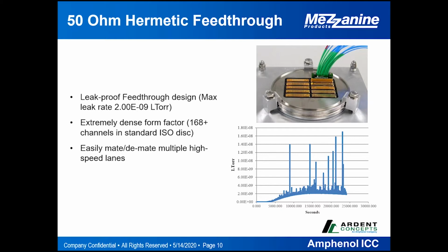This 50 ohm hermetic feed-through design allows us to stack multiple feed-throughs in a single isolation disk, allowing you to bring in or escape up to 168 or more channels through a standard isolation disk, depending on the layout of those hermetic feed-throughs in the system. This allows you to easily mate or demate multiple TR Multi-Coax systems and multiple high-speed channels.